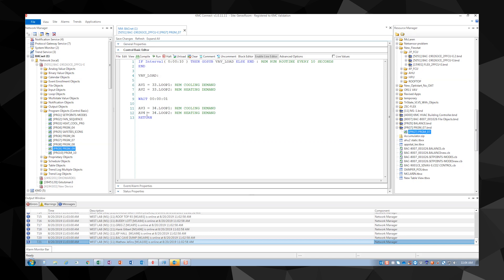There is a wait command between each device instance in the code. This forces the entire program to wait for the specified amount of time, in this case one second. Using the wait command throttles the number of messages or requests that are put out on the network and allows us to keep our network moving quickly.